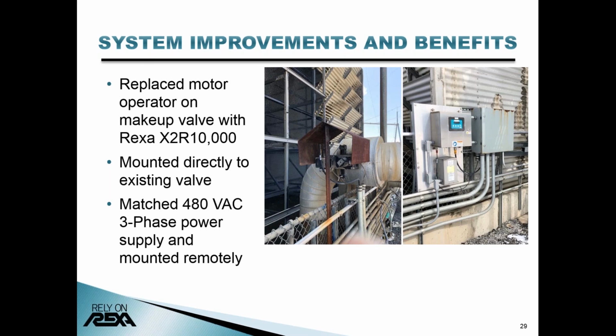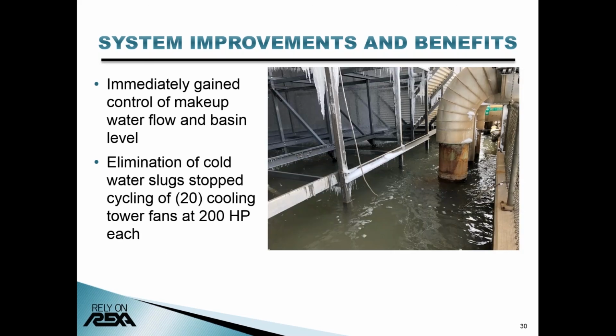Well, that's terrific. From what I've seen, you immediately gained control of makeup water flow to the basin, and I learned that the excessive cycling of the cooling tower fans in colder weather was completely stopped. Is this true, and were there any other benefits? There were several benefits, especially in the shoulder months where we are near approach temperature. We were cycling the fans on the cooling tower, stopping several times an hour. For a continuous operation plant like ours, we were leading into maintenance issues and preventative maintenance periods on these fans.